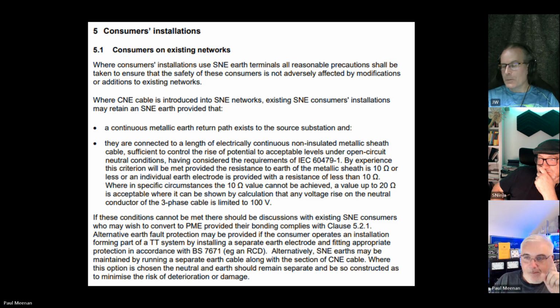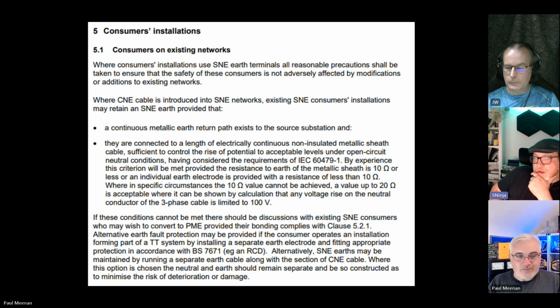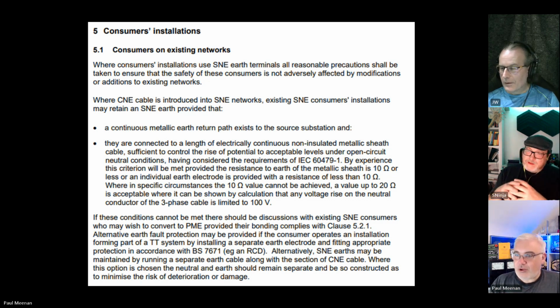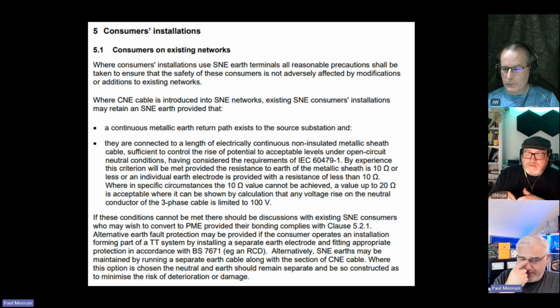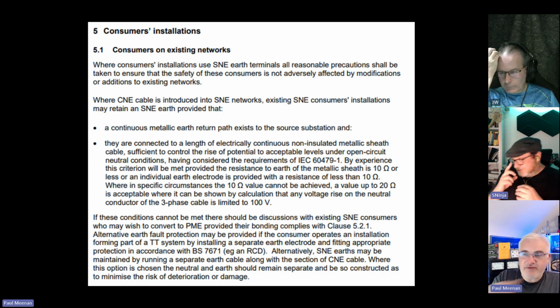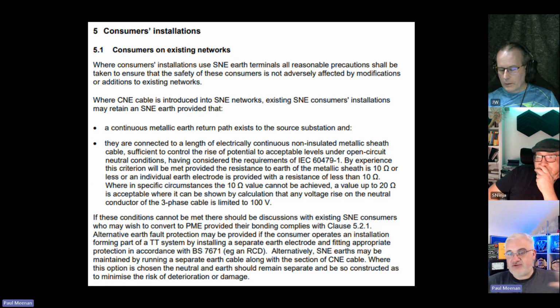So this is my problem. This document says it sits above 7671, but it's based on their experience. Really, this is just modification work. It's just jointing, and these guys put in the cable, they put the rod in the ground, and then they scarper. I did a piece of work with Eddie, where we had problems. The DNO come out, they stick their earth rods in, 4 of them, hope to get less than 10 ohms, and away they go. All they're trying to do is minimize that step voltage around that building. So they're relying on their TNS, those lead conductors, to give them 10 ohms. If they can't fix it, they just try and reduce the resistance via other earth connections.